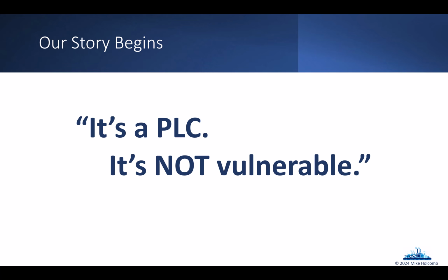So I had 5, 6 different PLCs that I used as part of my testing in my thesis. I talk about 2 in the paper, but I had 6. And each one, even if it was in their equivalent of run mode, when you went to make a change to the programming on the controller to change its logic, it would say, hey, you're in run mode, and normally you shouldn't make changes to the running code, but if you want to, just say yes and we'll make the changes. So having it in run mode didn't prevent any of those changes from actually being made.